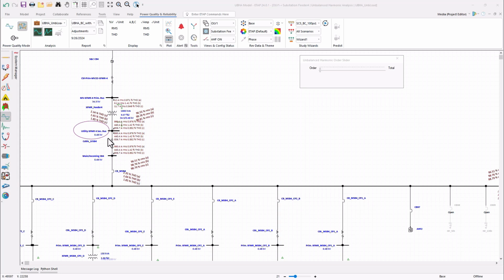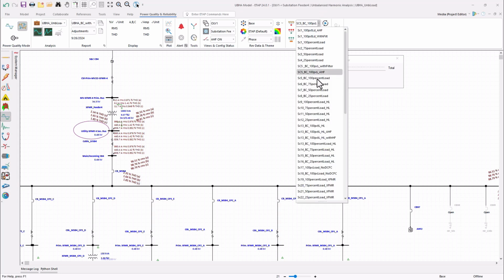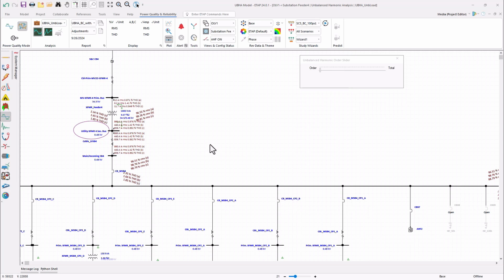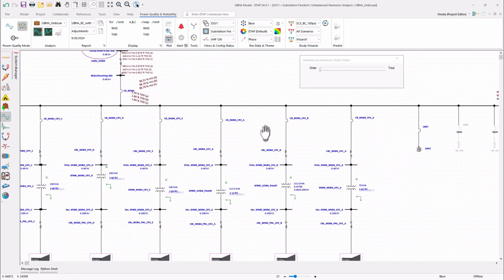Similar to this PCC location, there are other locations in the systems and in all different sites. For all the scenarios that were set up, among them, several of them had PCC locations where either voltage or total current harmonic distortion violations were noticed. And for all those cases, similar solutions were recommended to the client for mitigating the effect of harmonics and the distortions well within the limits provided by the standard. With that said, let me take you to the transformer K-factor calculation that was also performed as part of this analysis in the project, and recommendations were provided to the client in terms of K ratings of the transformer.